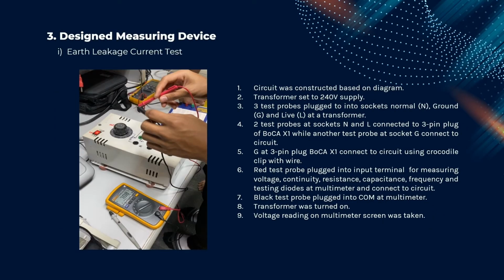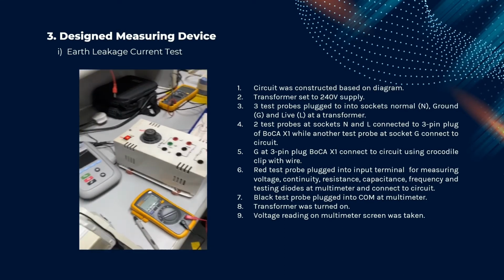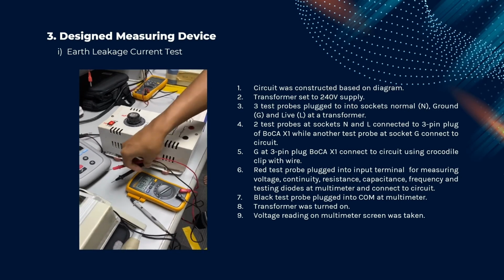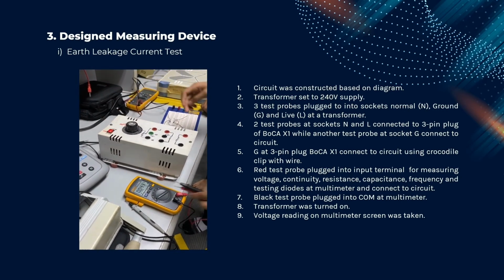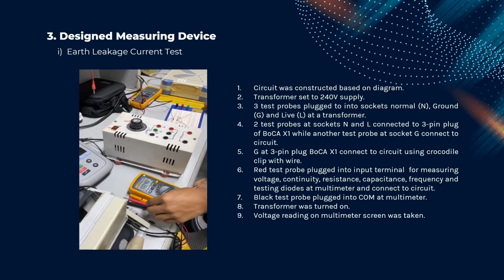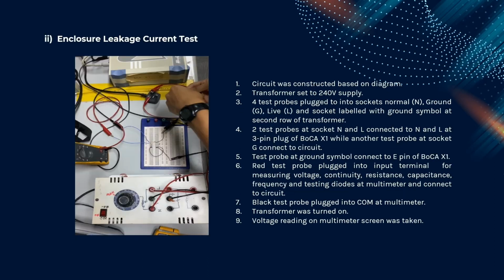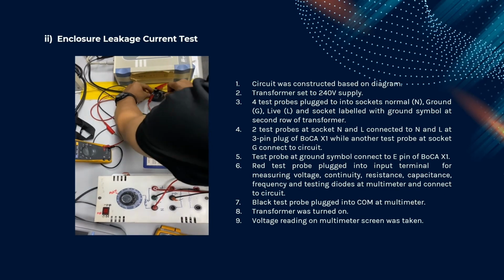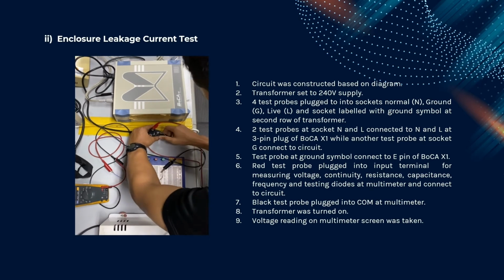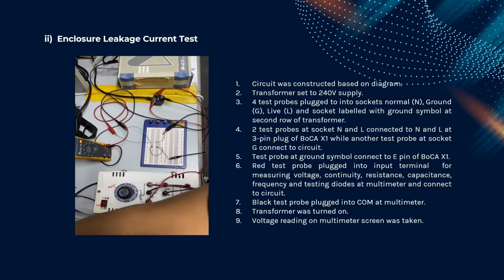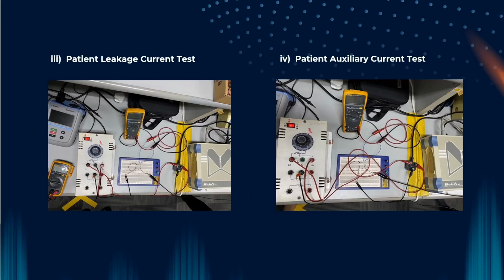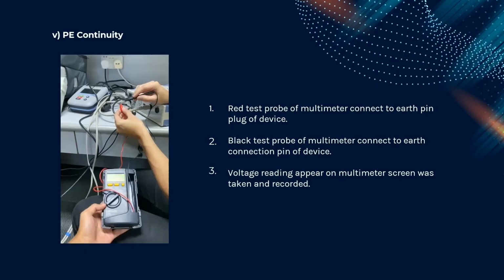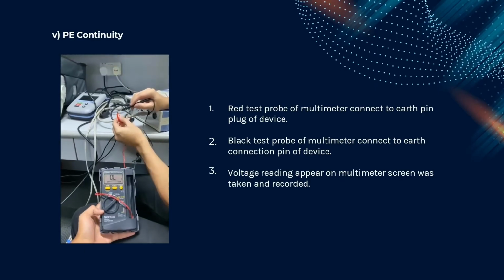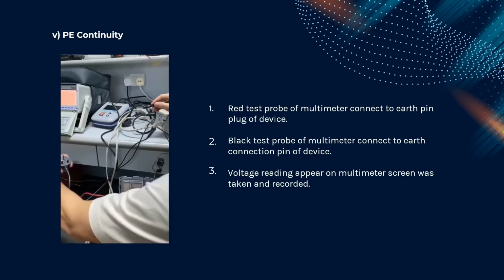Last, for the designed measuring device, we have designed a circuit following the IEC 60601 standard to test all 4 leakage currents. First, for earth leakage current, here is the test procedure. Okay, switch off the switch. Do this every time you finish recording one. This is the enclosure leakage current test. We also measure the patient leakage current test and patient auxiliary current test. Last but not least, we also do the protective earth continuity test by using a multimeter. Okay, continue.